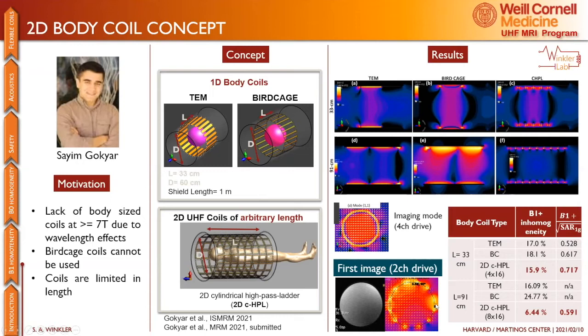But when you think about it, in quadrature mode the wavelength around the body coil is actually comparable to the circumference of the coil. So it's normal to have signal fall off here in quadrature mode. So this agrees nicely, and now we're working on an 8-channel prototype and hopefully soon some in vivo results, given the fact that we don't have the scanner here yet. But yeah, B1 homogeneity improved by a lot, and actually SAR is also improved, which is a good result.